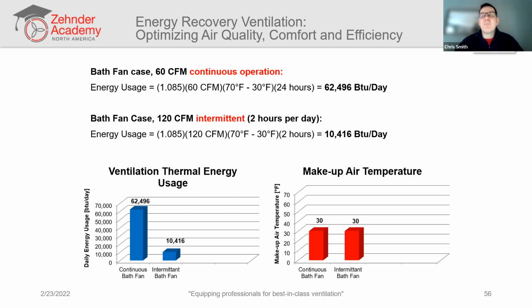Now, if the bath fan is used more commonly, where it's not even used continuously, it's only used, say, 2 hours a day to provide intermittent ventilation, well, yeah, we'll reduce the thermal energy usage. So we'll reduce the energy penalty of that sort of ventilation to only about a little more than 10,000 BTUs per day. Now, if you remember what our charts look like, though, we'll expect to see much more CO2 and VOC levels inside that space because we're not doing continuous ventilation.